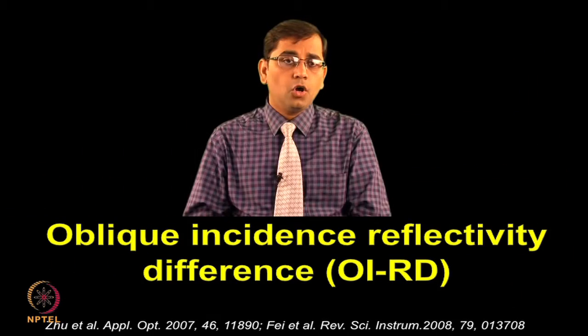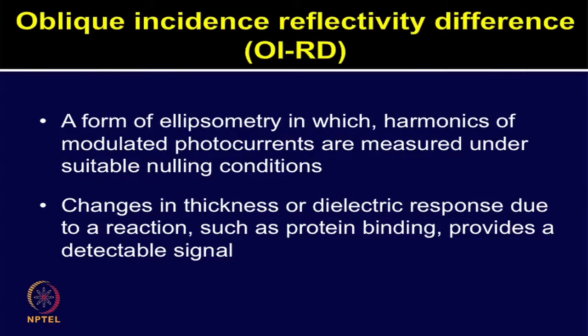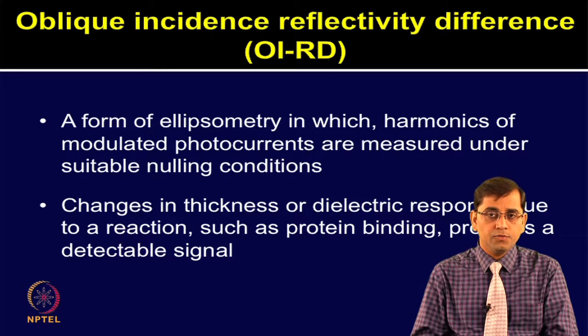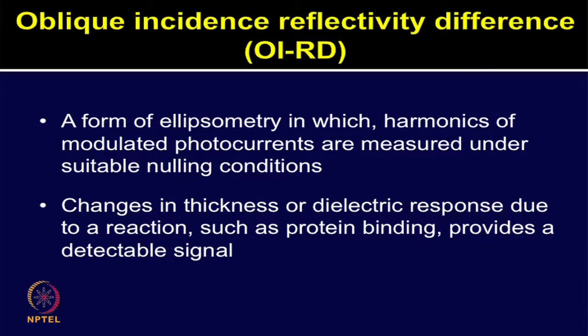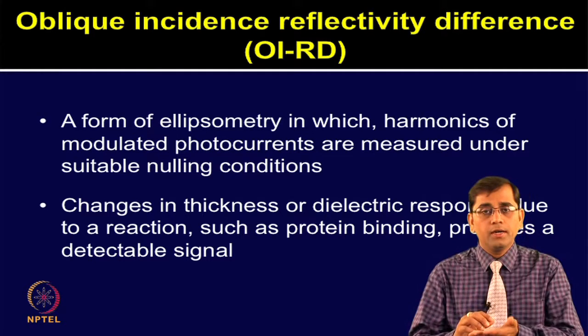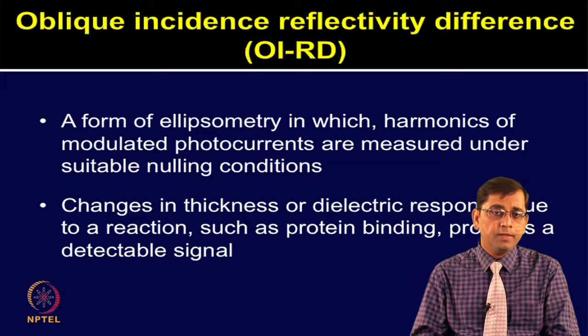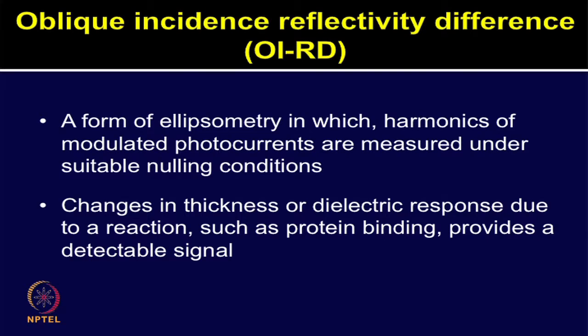Let us talk about oblique incidence reflectivity difference, or OIRD. OIRD is a form of polarization-modulated imaging ellipsometer, in which the harmonics of modulated photocurrents are measured under suitable conditions. It can be used for label-free, high-throughput detection of biomolecular interactions on DNA as well as protein microarrays. Changes in thickness or dielectric response due to a reaction such as protein binding provide a detectable signal, allowing reactions to be monitored.